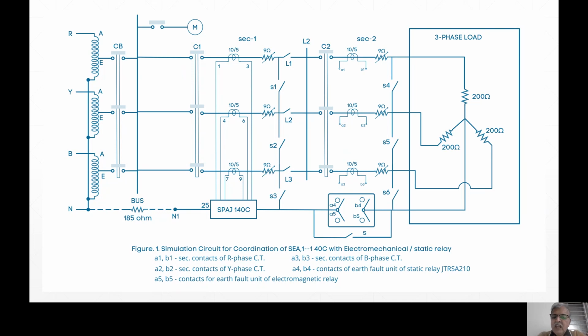Similarly, in the earth fault version, I've got a selector switch, and using that selector switch I can go either for an electromagnetic relay or for a static relay. That is, the digital relay SPAJ will coordinate with the electromechanical relay. We designed this experiment somewhere in 2000 or 2002. At that time, electromechanical relays were still available. Now, more or less, they are not available, so this is not a requirement now. But at that time, you had to coordinate a static or electromagnetic relay with a numerical relay. So we had designed this experiment for coordination purposes also, right? So, simple circuitry.